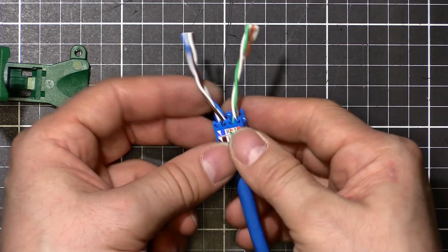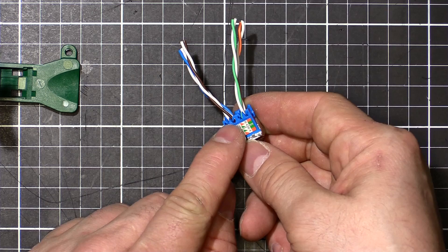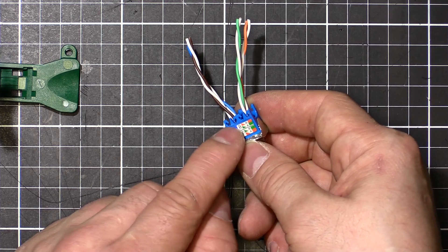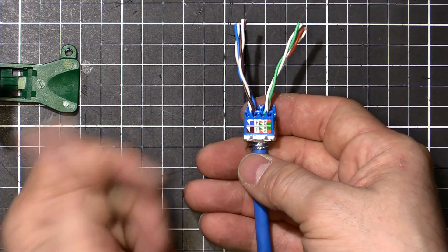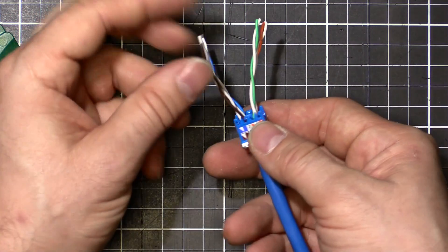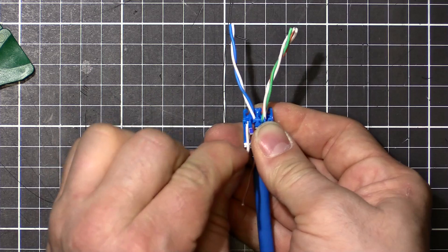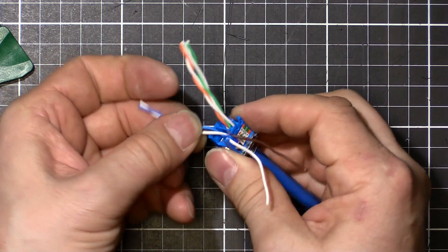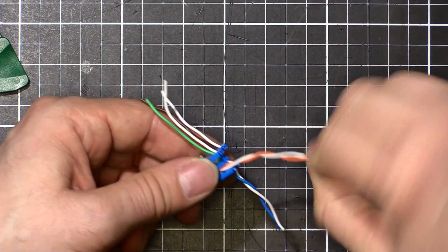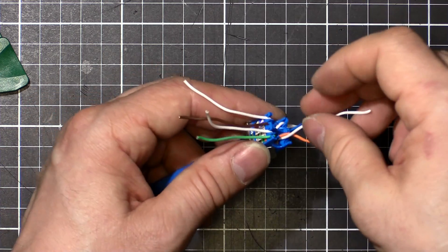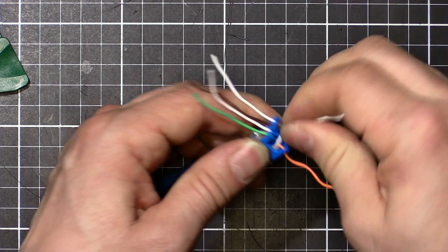Alright, now what we have to do is bring these wires down and through the little catches here. You see, along here, little tabs, like little barbs. On all of these, the white wire is on the left. So if you untwist your wires, don't untwist them too much. You want to keep the twist up to as close as possible. We go straight down, just like that. Now same with all the rest. If the white is on the incorrect side, I like to just give it a little bit of extra twist rather than untwist, just so we make sure we don't get any interference because it's untwisted too much.